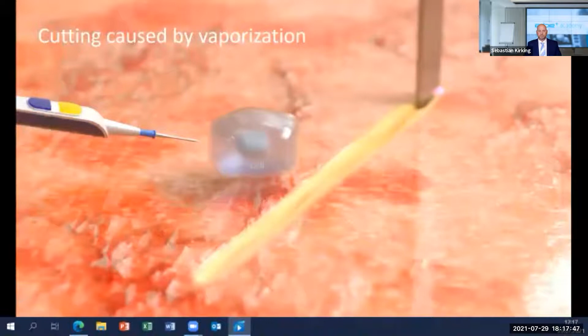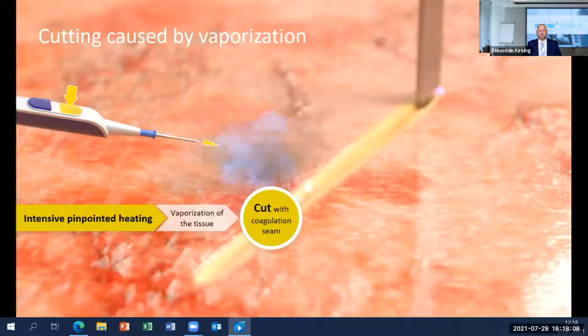Depending on the selected settings, the current can heat up the tissue almost instantly to several hundred degrees Celsius. At this high temperature, the tissue vaporizes at the point of contact. This serves to cut and dissect the tissue. The lateral heat spread that comes with the cut adds additional coagulation. This also helps to minimize bleeding. The intensity of the lateral coagulation depends on the settings that I will explain later.